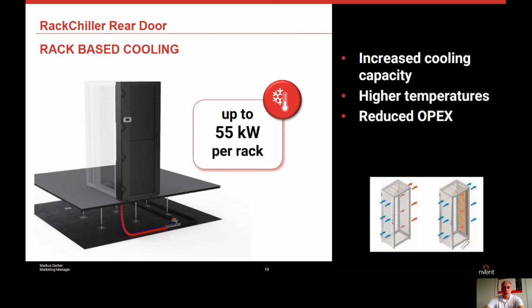What the cooling solution is doing is that you put a coil on the rear side of the rack, which replaces the rear door. In this coil, a liquid flows. The heat from the fans of the equipment is pushed through this register. The heat is transferred to the liquid circuit and is taken away. So the air is cooled down when entering the room. This means you have the same stable level of temperature in the room. And moving closer to the heat already allows higher liquid inlet temperatures, which reduces your operational costs.